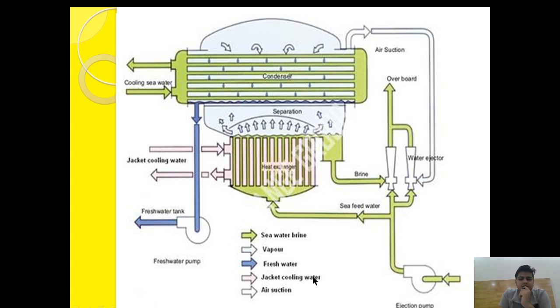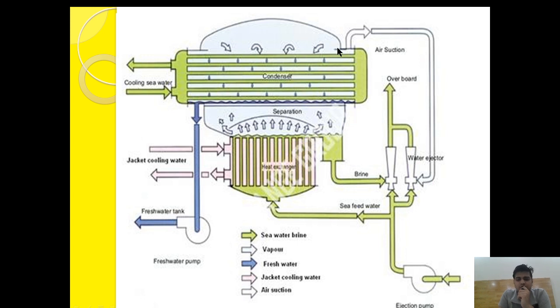This is the diagram of a Sasakura manufacturer fresh water generator. The sea water pump feeds sea water to two vertical tubes — vertical tubes are provided to ensure the vapor formed passes without restriction directly upward. Jacket cooling water and sea water exchange heat, vapor is formed and filtered by a demister plate, then passed through a condenser. The same sea water line is used for cooling the condenser, and fresh water is collected in a tray. The brine ejector and air ejector remove excess brine and air to maintain vacuum condition and correct water level.